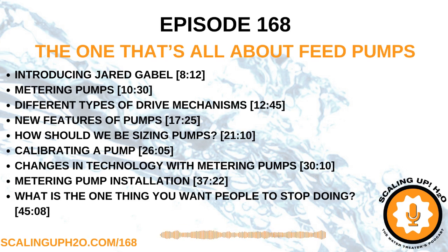And you know, I can't help but think of a story when, I believe it was a PVC head that we had, and we were using a phosphonium-based biocide, and they did not play along very well together. We were doing some field testing for a company, and they had just let an employee go, and we all thought that he had come into the mechanical room and hit these pumps with a baseball bat. I mean, it just shattered all the stuff. Of course, it was bad materials choices. So you definitely have to know what you're using and what's the right materials, and that they're compatible.